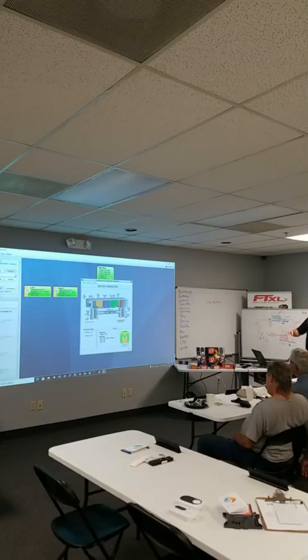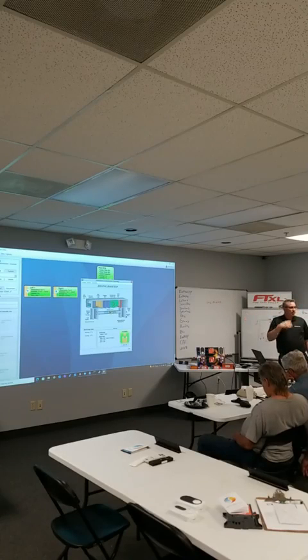You can override the fan on and off from here. In the network controller, it can do trends, it can do alarms. So for example, if you wanted to say my unit's occupied, fan start-stop is on, but fan status is off, I want an alarm, you can do that. There's a lot of different things to do. You do dirty filter alarms too with the differential pressure sensor. Yeah. You get alarms when the filters are starting to get clogged.